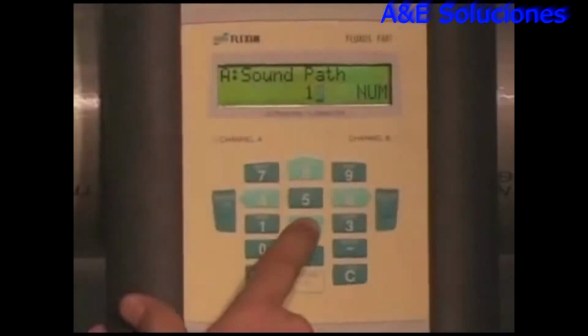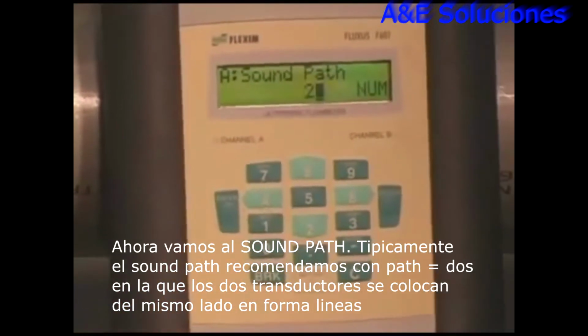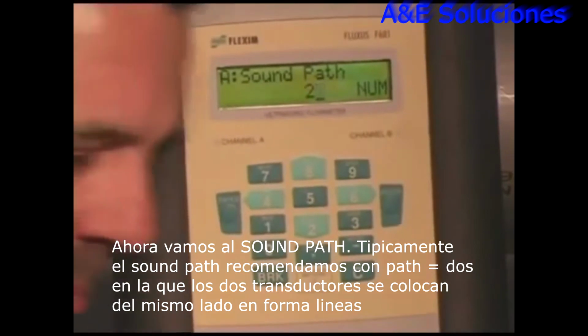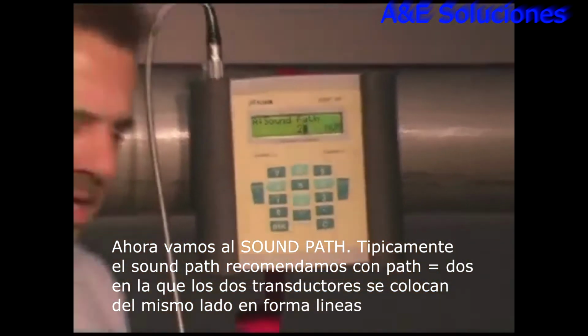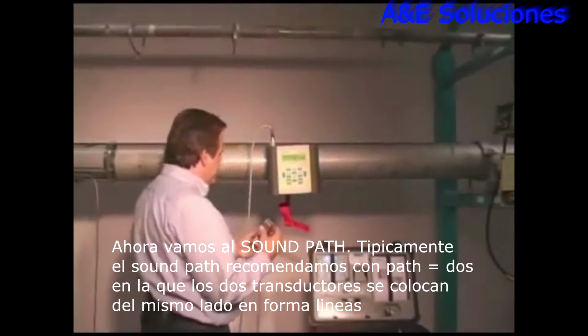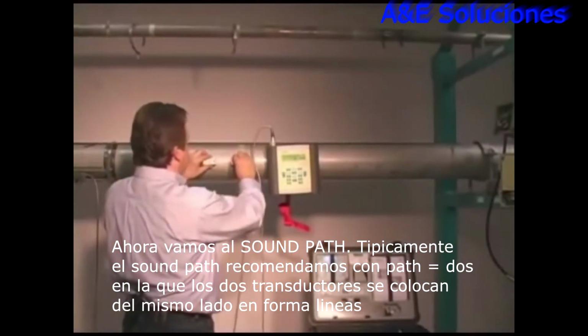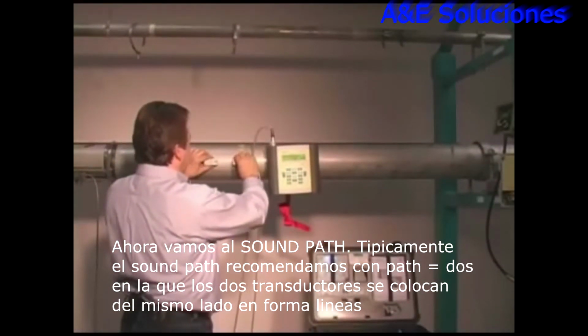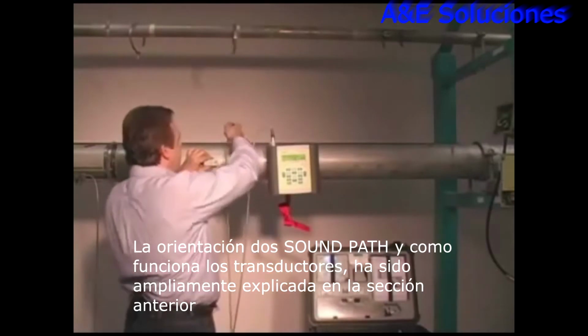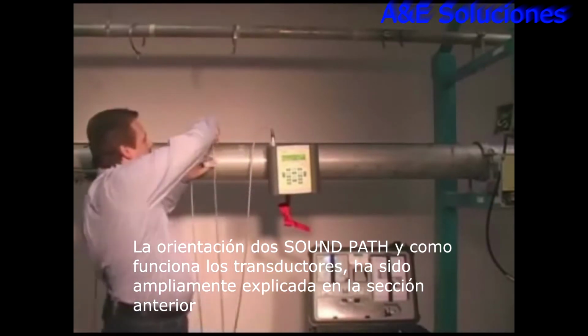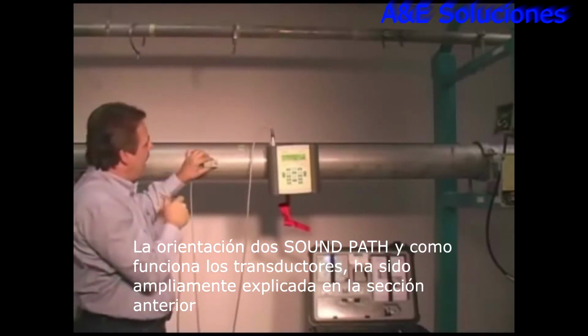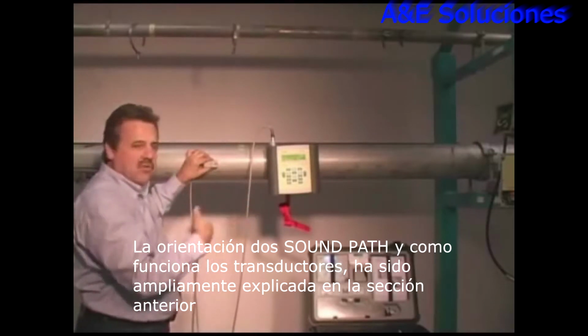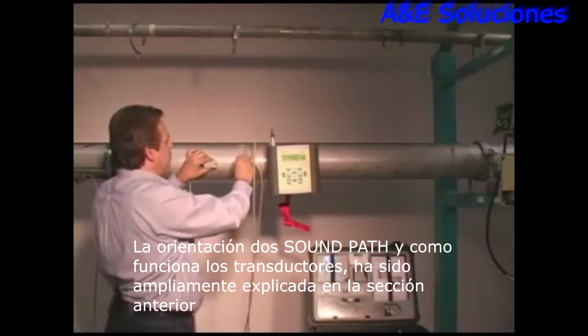Now typically, we recommend starting with 2 sound paths. Now 2 sound paths is when our transducers are on the same side of the pipe. One sends a sound beam out, it echoes off the far pipe wall and comes back to the receiver, and it's taking 2 round trips through the pipe, and that's why it's called 2 sound paths.